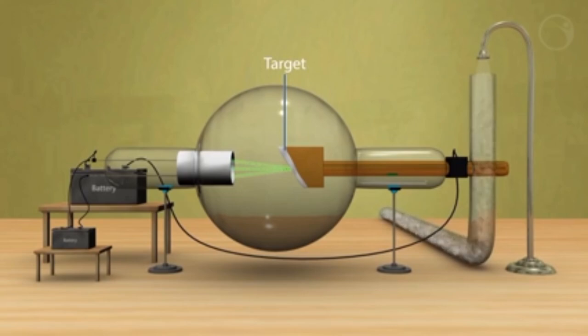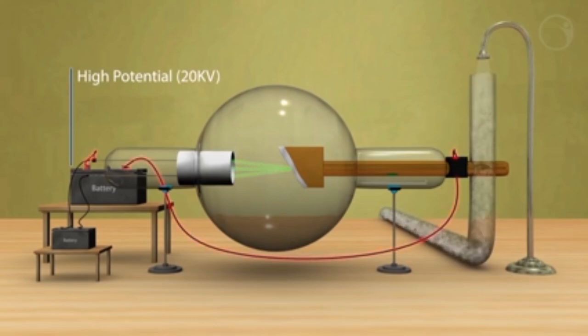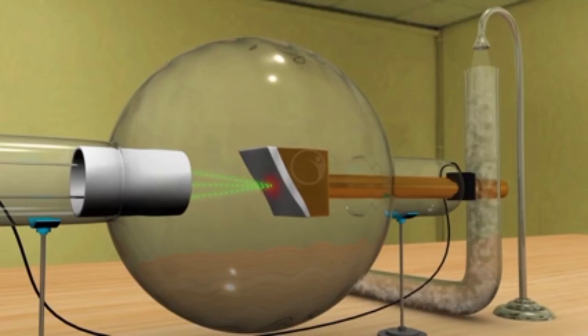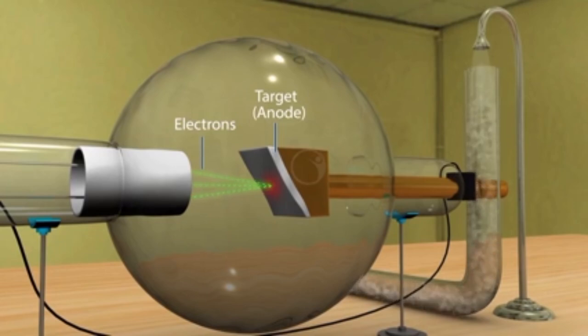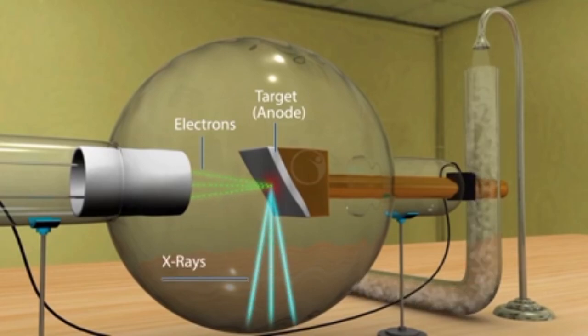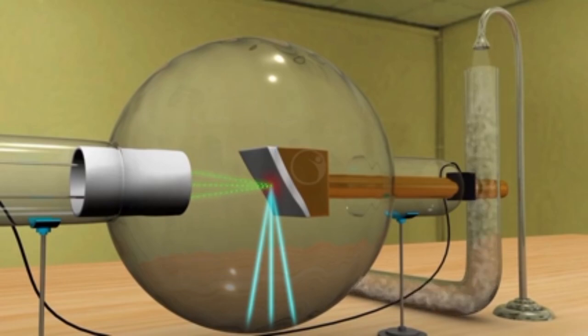The target is also tilted at an angle of 45 degrees, causing the electrons to hit at an angle. This will produce the X-rays almost perpendicular to the electron beam. A very high potential of 20 kV is applied between the source and the target. Due to the high potential difference, the electrons are accelerated towards the anode and it hits the metal. When it hits, the kinetic energy is transferred to produce X-rays. The intensity of the X-rays depends on the number of electrons striking the metal target. So, if we can increase the rate of electrons emitted by the filament by increasing the current flowing through the filament, then we can increase the intensity of the X-rays.